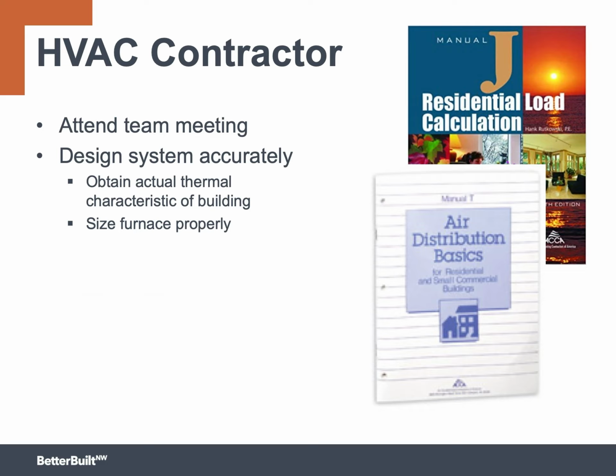The exact insulation levels, the window U values and solar heat gains, and the window orientations are all key factors. Air leakage is one of those things that gets missed quite often because in most of the Manual J software, you don't have an actual number for air leakage. It says something like very tight or very loose. In the past, a typical production home might have had an air leakage rate of 7 or 8 air changes per hour at 50 pascals.